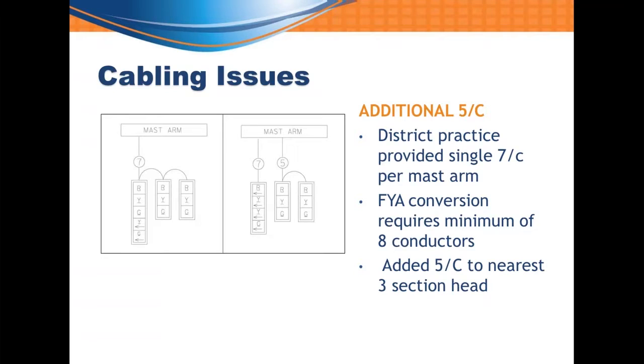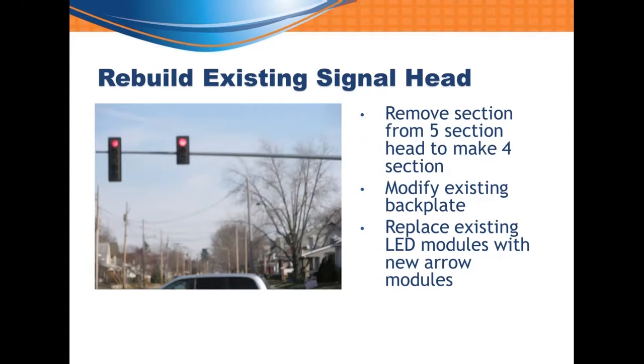One issue we ran into during design was our cables. Standard procedure was to run a single seven-conductor cable out the mast arm to the shared signal face — it had enough conductors for both through and left turn movements, with jumpers back to the other heads. But converting to flashing yellow arrow, that seven-conductor no longer satisfied the requirements, so we had to add an additional cable. We repurposed the seven-conductor for the flashing yellow arrow head and added a five-conductor cable for the through movements.